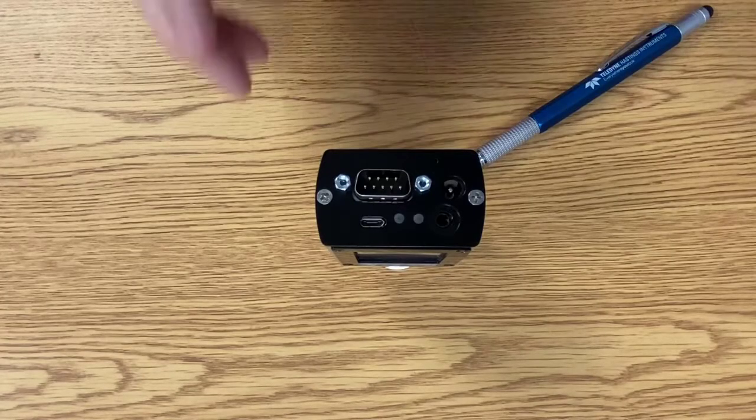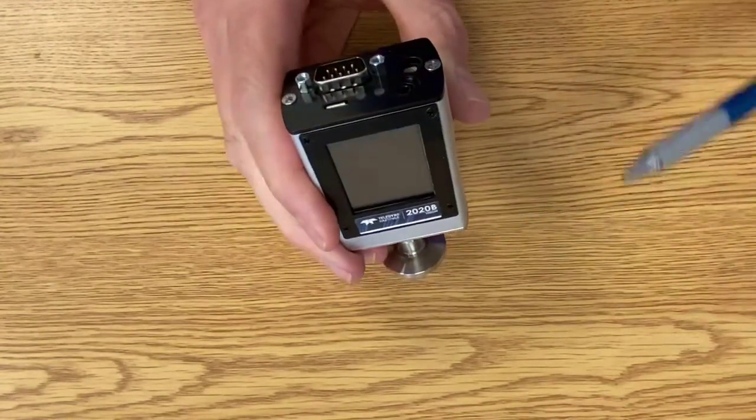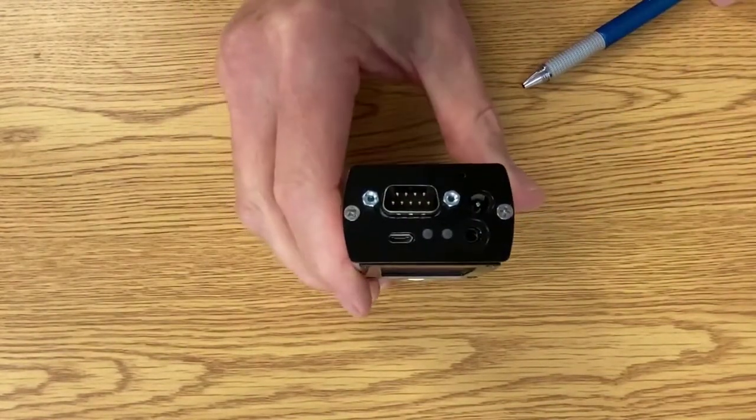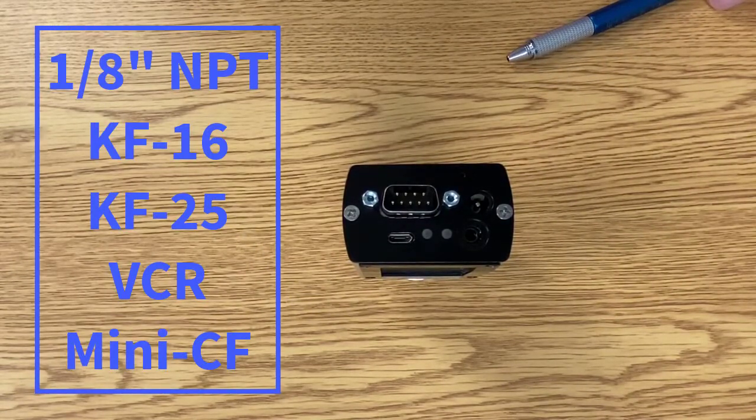So, this model has been built with a KF-16 flange, but we can provide a number of different system connections, including 1/8-inch NPT, KF-25, 1/4-inch and 1/2-inch VCR, and MINI CONFLAT.